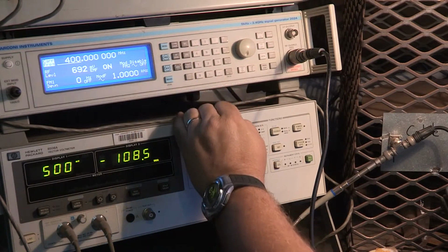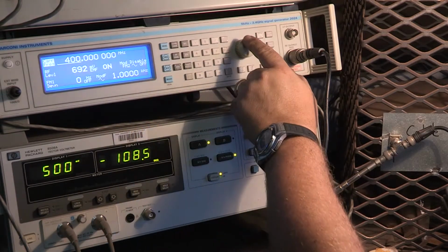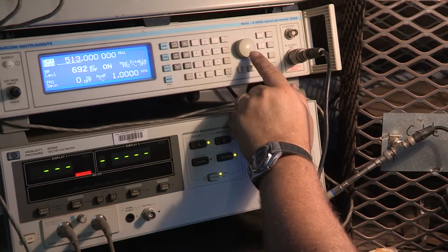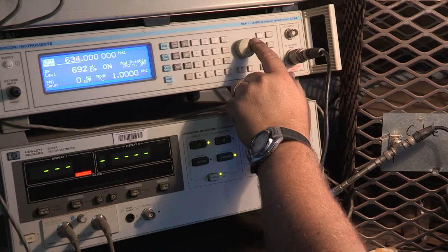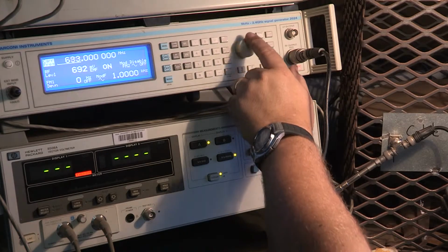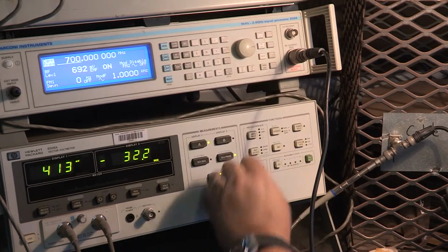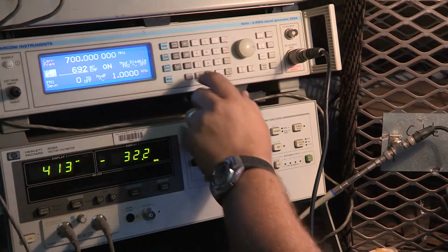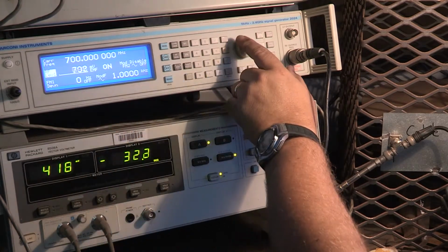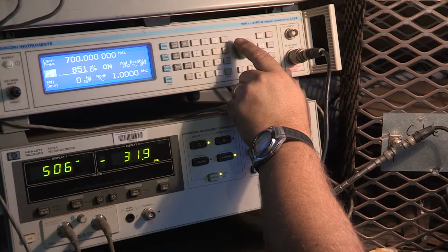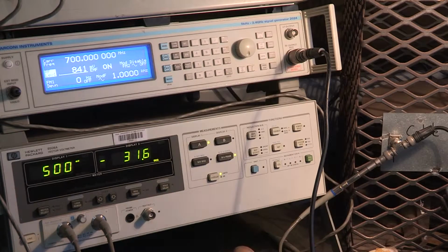Then we go to the next input frequency, 700 megahertz. You see where this cable is going with its readings? You could have taken frequencies in between and so on. I'm quite happy with this range of frequencies because we want to see the effect. And then we notice our input has changed again, so we make sure it goes back to as close as possible to 500.